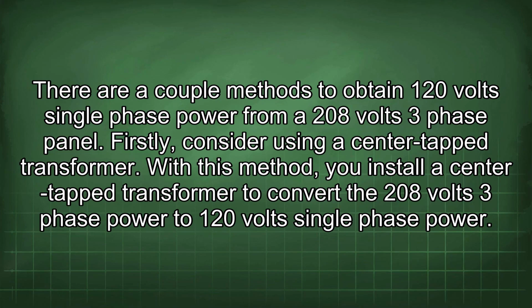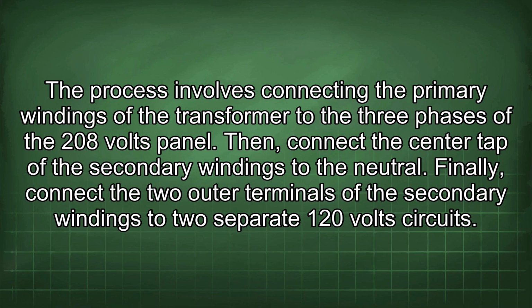There are a couple methods to obtain 120 volt single-phase power from a 208 volts three-phase panel. Firstly, consider using a center tap transformer. With this method, you install a center tap transformer to convert the 208 volts three-phase power to 120 volts single-phase power. The process involves connecting the primary windings of the transformer to the three phases of the 208 volts panel.